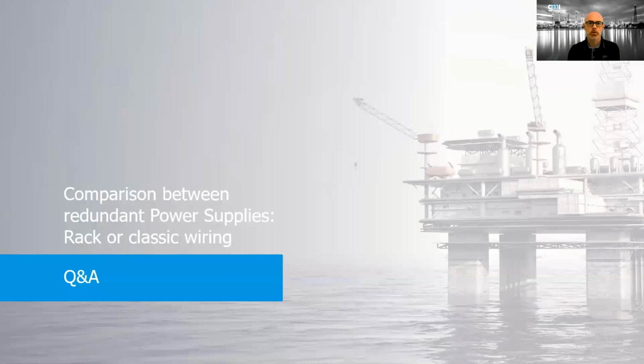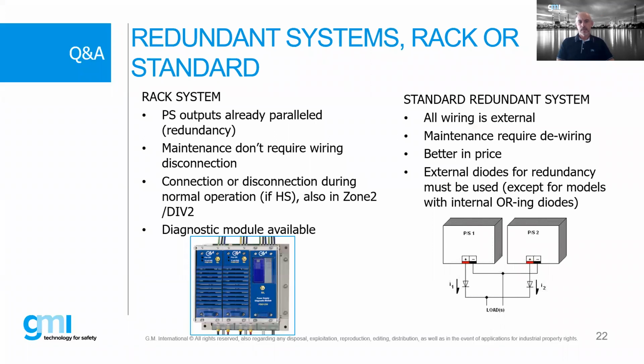Well, another question that our customers often ask us is the comparison between redundant power supplies, rack or classic wiring. Also in this case, there are two possibilities. For instance, let's talk about the standard redundant system on the right side. You have two power supplies, and outside you have the OR-ing diodes for redundancy that need to be connected if you want to parallel the load sharing for the power supplies connected.